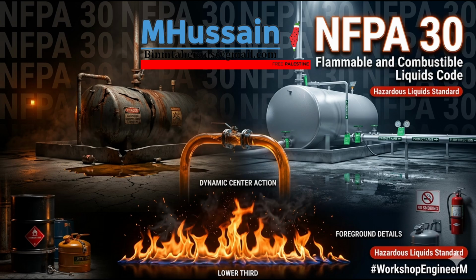That tenant vacates the property and a new tenant signs a lease. The new tenant manufactures alcohol-based chemical reagents, highly volatile, Class IB and IC liquids. The physical footprint of the building hasn't changed an inch, but the internal risk profile has just undergone a magnitude shift. The liquids have completely different thermodynamic behaviors. If the property manager just hands over the keys without engaging an engineer to meticulously reevaluate the existing space against the strict mandates of NFPA 30, the facility instantly transforms into a ticking time bomb.